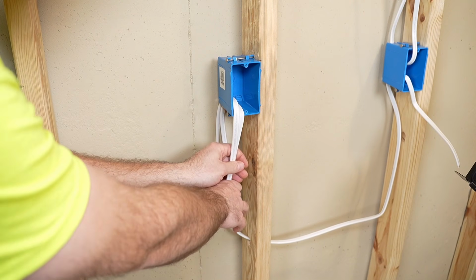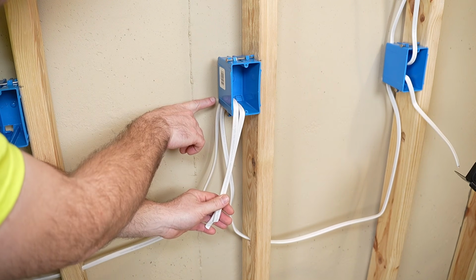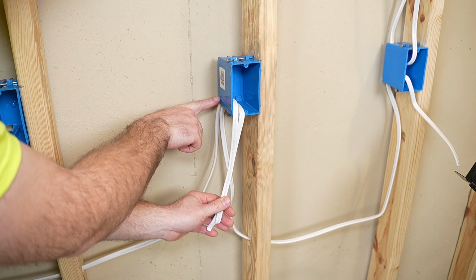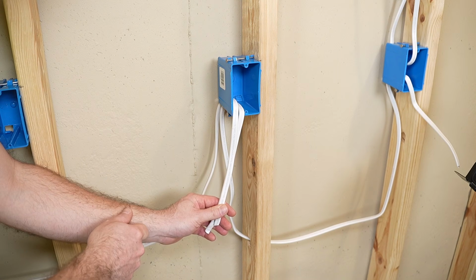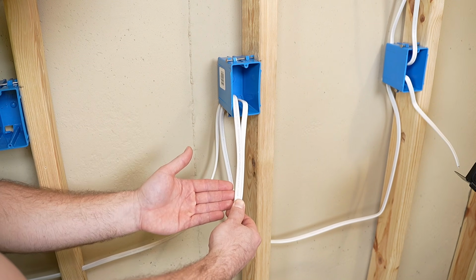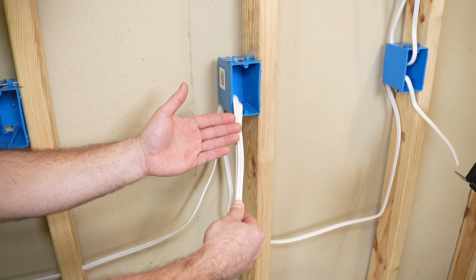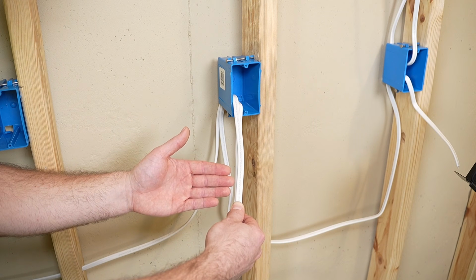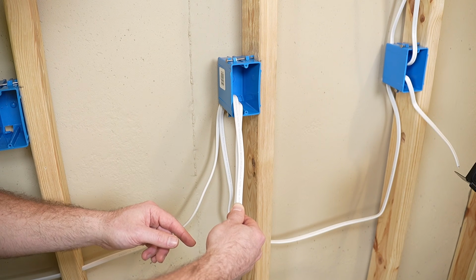Again, make sure there is enough wire here to have at least 6 inches from the back of the box to where we're going to cut it for the receptacle. Don't think of leaving extra wire as wasteful. Think of it as cheap insurance so you don't have to re-pull wire later because one of your cables turned out too short.